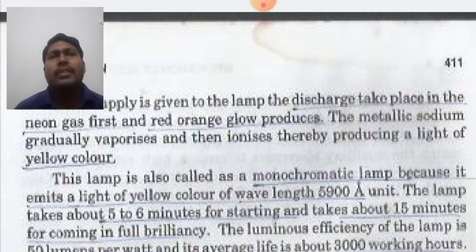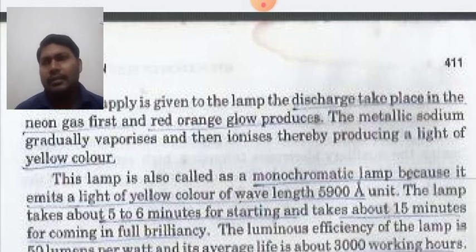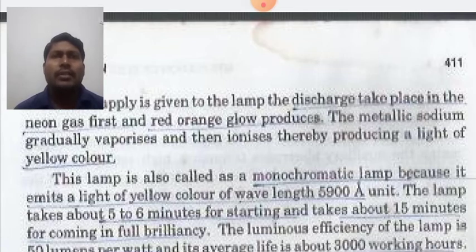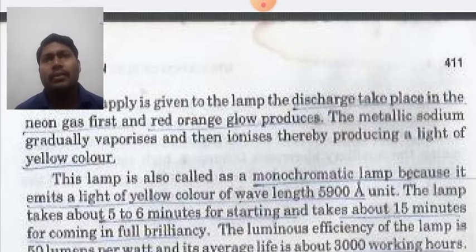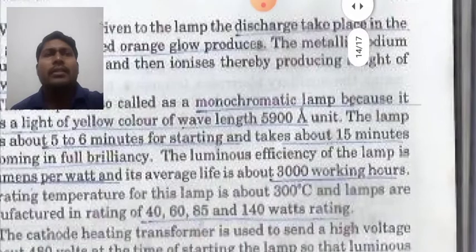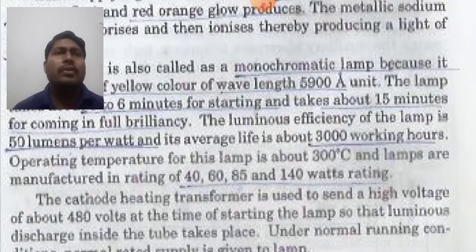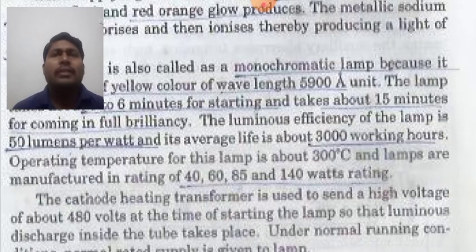These lamps were used earlier but are now discarded because power consumption is high and the starting time is considerably long — it takes five to six minutes during starting and about 15 minutes to reach full brilliancy. The luminous efficiency of the lamp is 50 lumens per watt and its average life is about 3000 working hours.